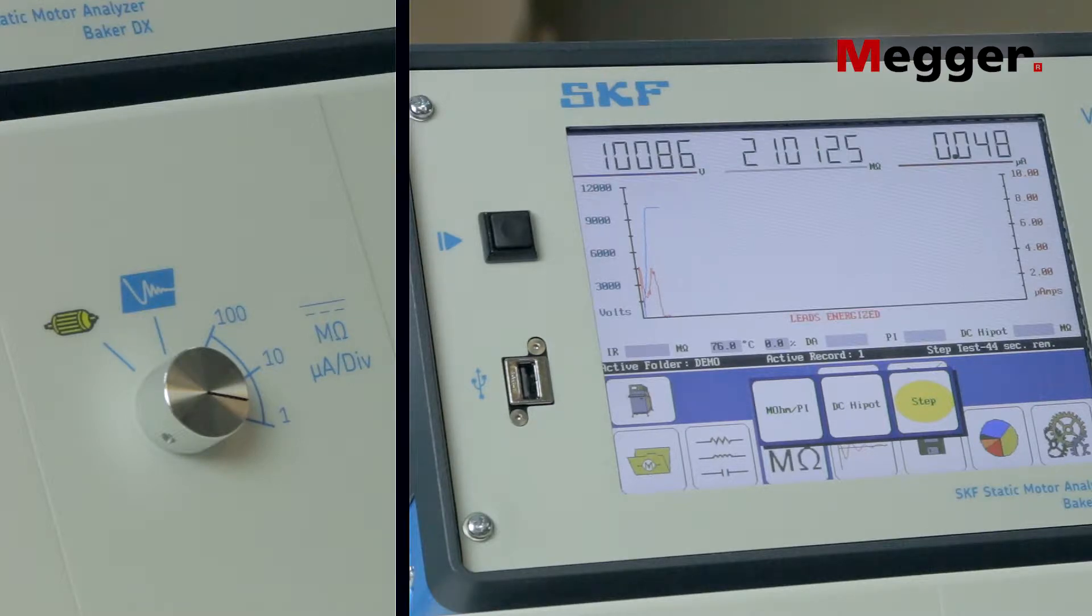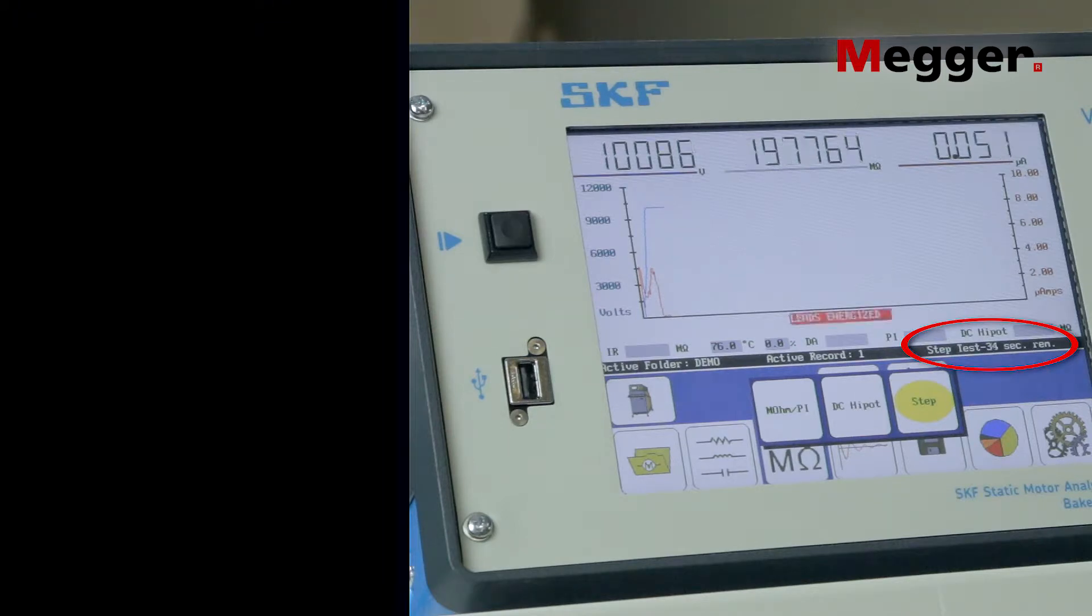The leakage current will continue to diminish, and if it again falls below half of the lowest division, turn the power pack's function knob to 1 microamp per division. Watch the seconds remaining countdown.